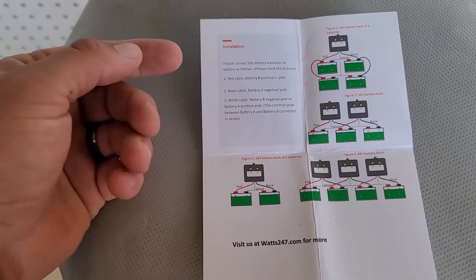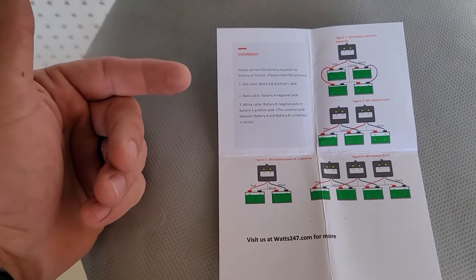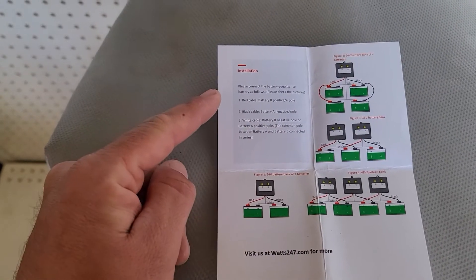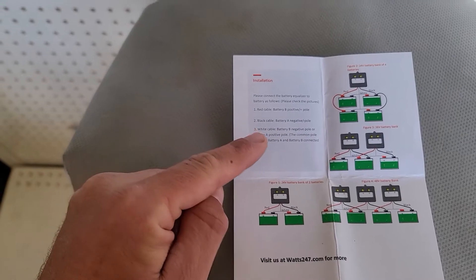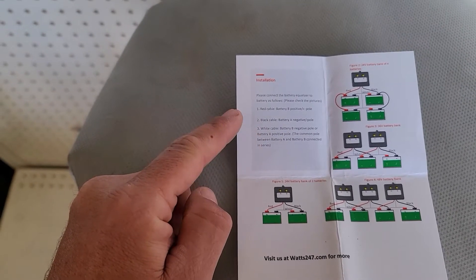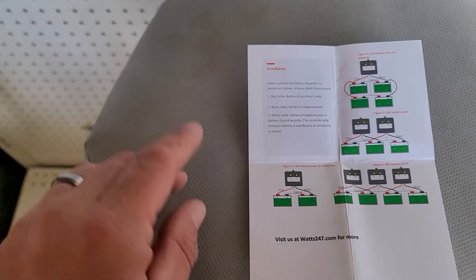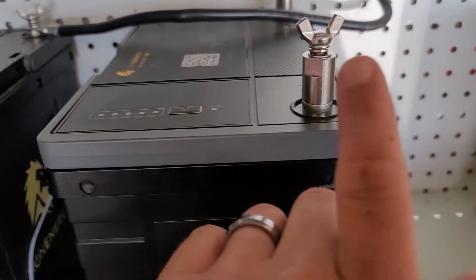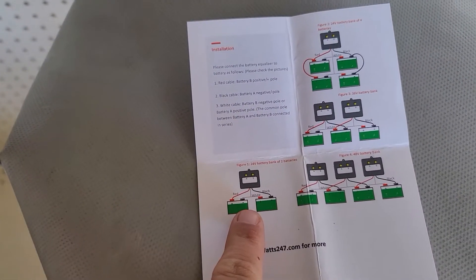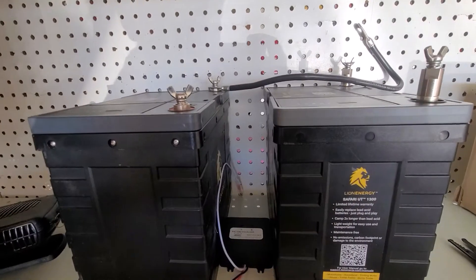Let's go to installation. It basically says to connect the battery equalizer to the battery as follows: step one, connect the red cable to battery positive pole. The black cable goes to the negative. The white one will be our last connection and that goes to the common between battery B negative and battery A positive.